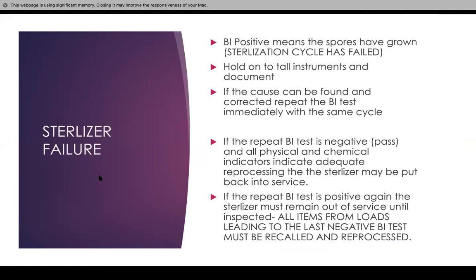If there is a sterilizer failure — a biological indicator that is positive means the spores have grown. If the biological indicator placed in the PCD shows a color change after being placed in the incubation device for 24 hours, that means your sterilization cycle has failed. You have to hold all instruments and document that it has failed, that you have held them, and that you have not released them.